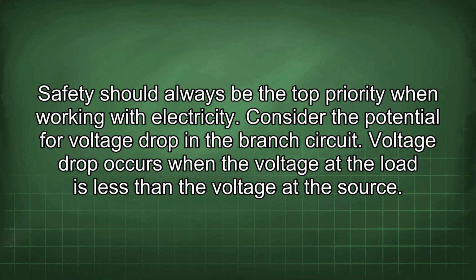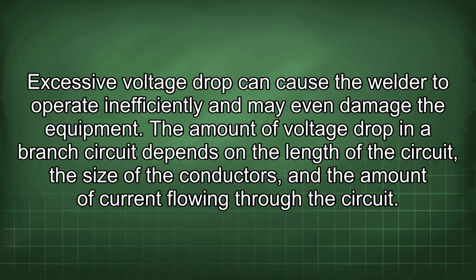Consider the potential for voltage drop in the branch circuit. Voltage drop occurs when the voltage at the load is less than the voltage at the source. Excessive voltage drop can cause the welder to operate inefficiently and may even damage the equipment. The amount of voltage drop in a branch circuit depends on the length of the circuit, the size of the conductors, and the amount of current flowing through the circuit.